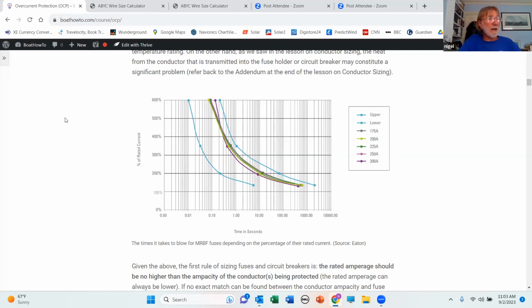So they shut it down and they got it back in. A single stainless steel washer in the wrong place had melted the fuse the first time around, destroyed both of those alternators, and was about to do the same thing over again. So every single boat I go on with a large number of ANL and Class T fuses, I look at every single fuse on both ends of it to make sure there's no stainless steel washers in there, and you wouldn't believe the number of times I see the washers in the wrong place. So you have to be really careful about that.